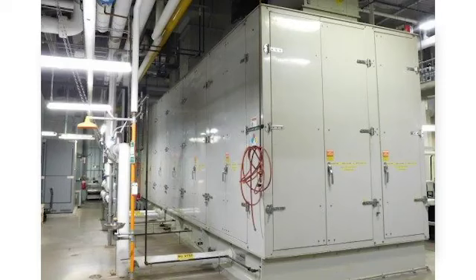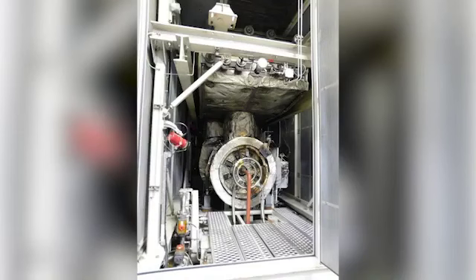Take you into the cogen room. This is where our gas turbine and heat recovery steam generator are located. We have a Mercury 50 gas turbine generator, and we'll show you the gas turbine. Off to the left in that picture is a dispatchable air inlet cooler. That air inlet cooler is one of the many tools that we have to utilize the thermal energy that we store in our thermal energy storage tank and to improve the overall Brayton cycle efficiency of the gas turbine.